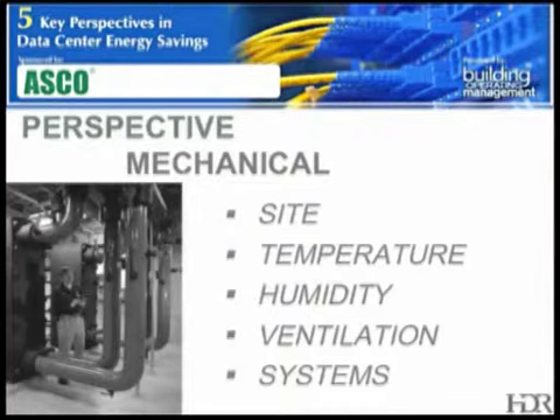And then finally, on the systems, the systems that we've applied are evaluated on a site-by-site, facility-by-facility basis. These have consisted of systems that were achieving reliability through simplicity, of course incorporating N+1 design for the components, but these would be things like air-cooled chillers with CRAC units within the space, DX crack units with remote air-cooled condensers, or possibly dry fluid coolers for the condensers.